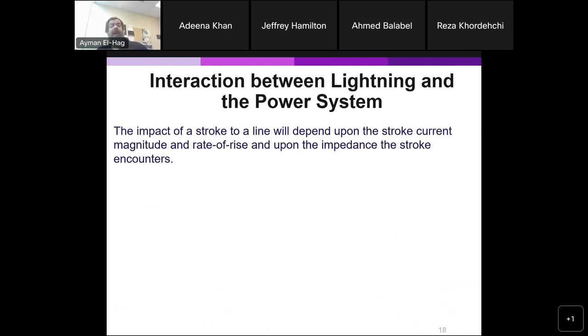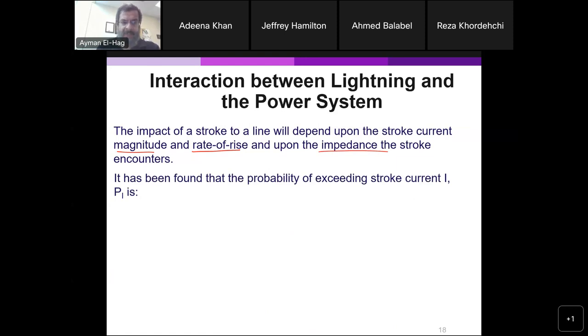Okay. Now, the impact of the stroke on a line will also depend on other factors, for example the current magnitude, the rate of the rise, and the impedance of the stroke. So when the stroke hits, it also depends on the surge impedance of the line and the surge impedance of the tower itself. Okay.